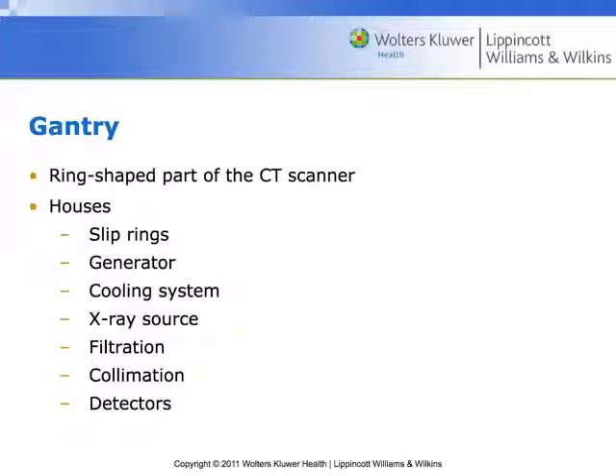Cooling systems are really critical to the CT tube and x-ray source because we're producing quite a bit of heat. We also provide filtration — typically the filtration we use is in what shape? A bowtie filter, because a patient is basically shaped like a hot dog.